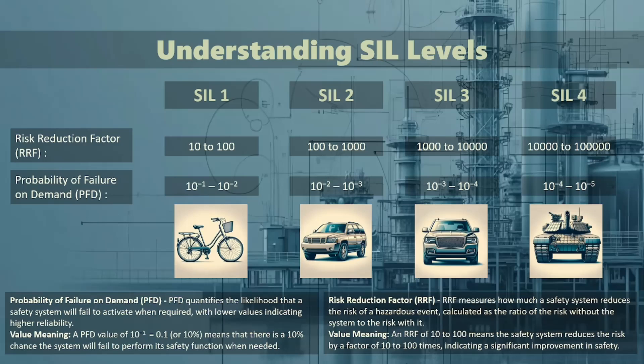SIL 3 is your high-end SUV, equipped with advanced safety features. It offers an RRF of 1,000 to 10,000, reducing risk by up to 99.99%. SIL 4 is the armored tank of safety levels, providing the highest safety with an RRF of 10,000 to 100,000, reducing risk by up to 99.999%. However, it's rarely used in practice due to its complexity and cost.